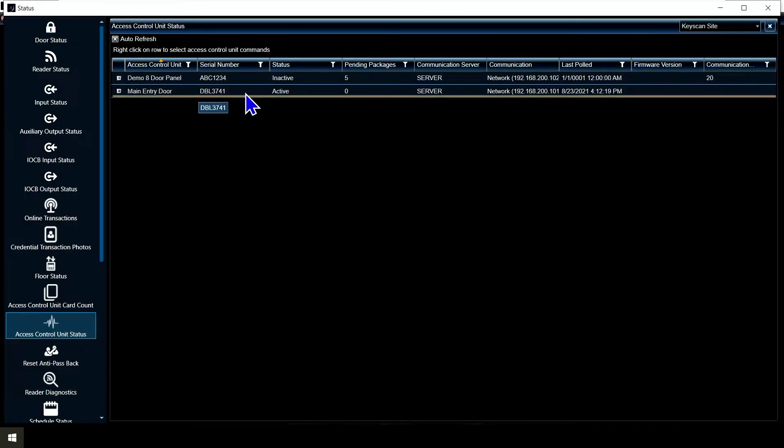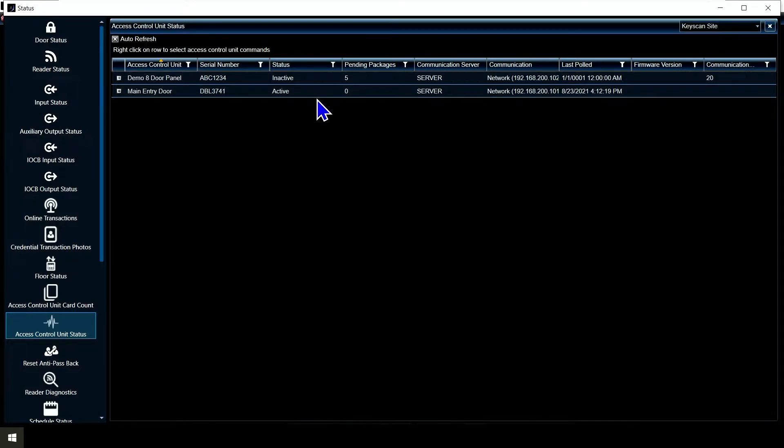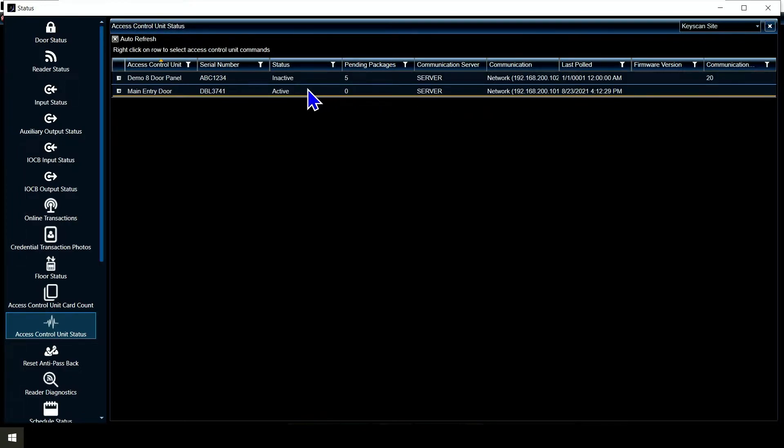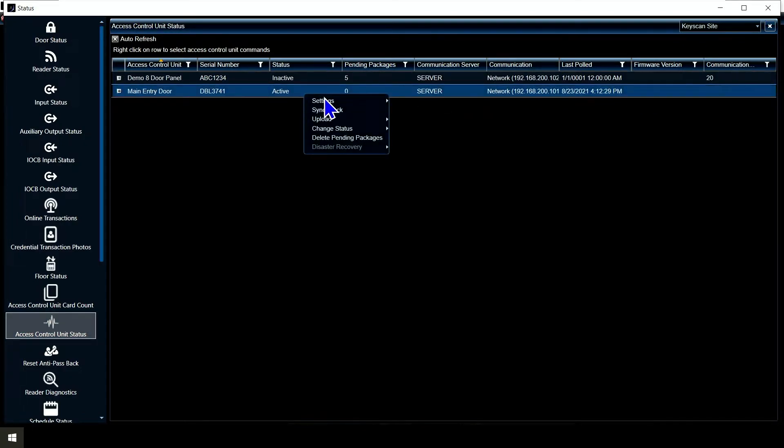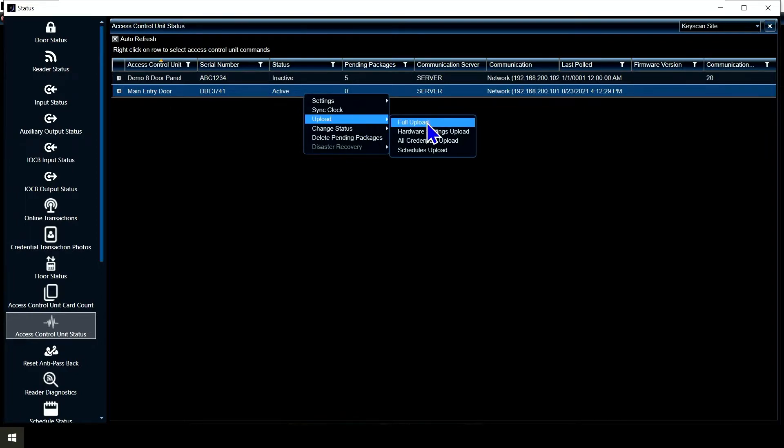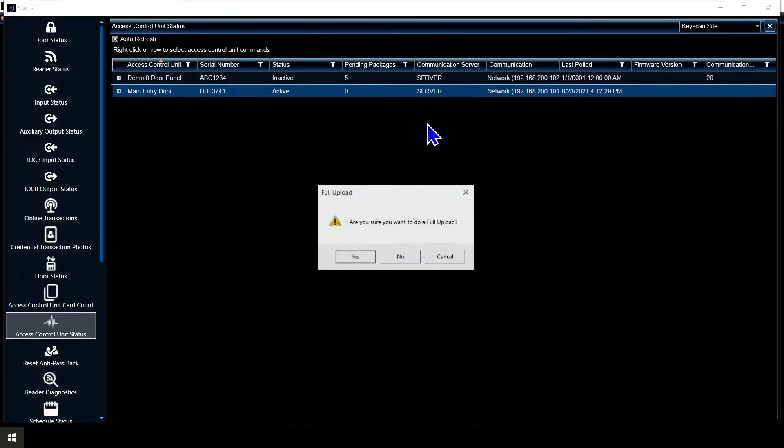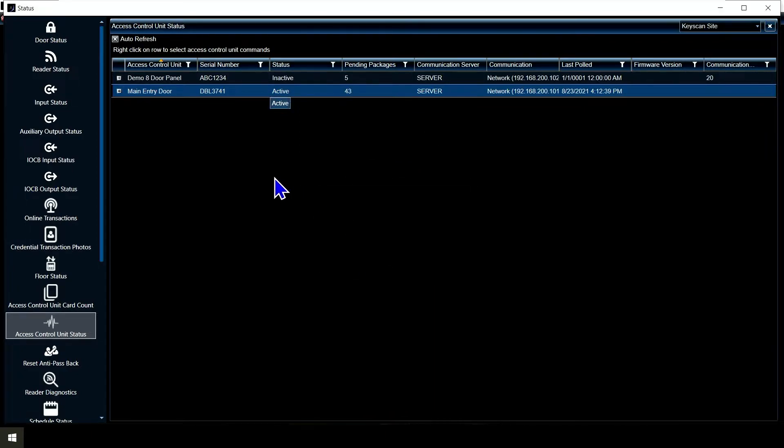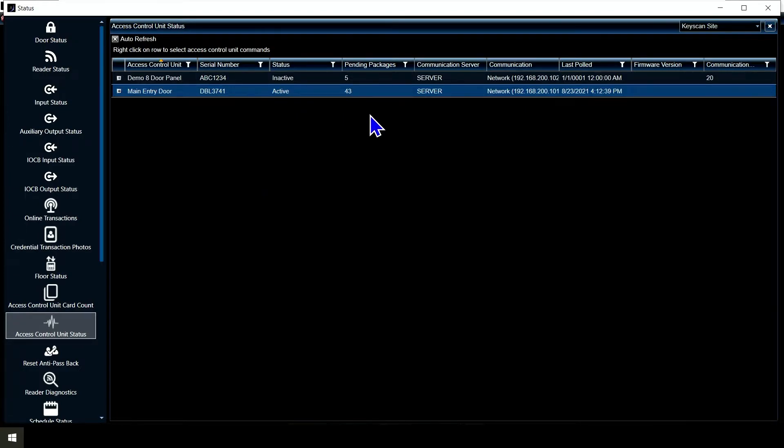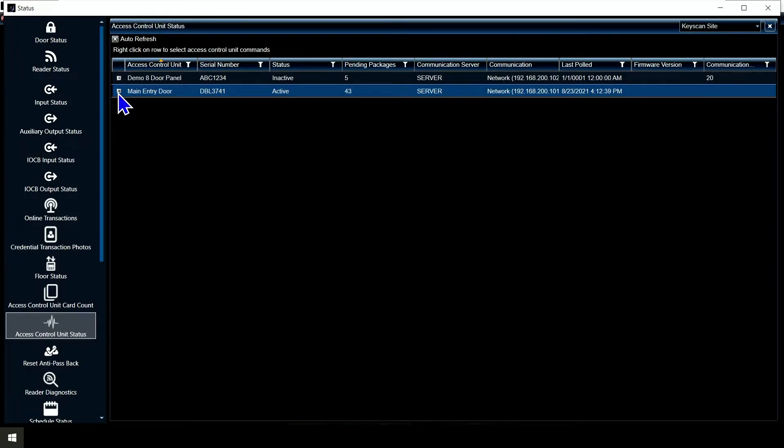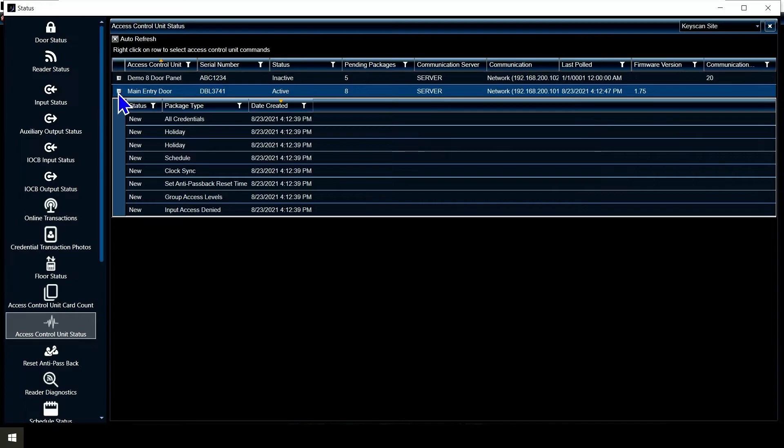Here beside me I can see the green light on it. Status is showing active, no pending packages, everything looks good. If I right click on it and choose full upload, it's going to say are you sure. I'm going to hit yes. There's 43 packets here, now it's going to start counting down because it's talking to the panel. We should see those start going away fairly quickly. Yeah, we see it just went from 43 to 8 pretty quick.